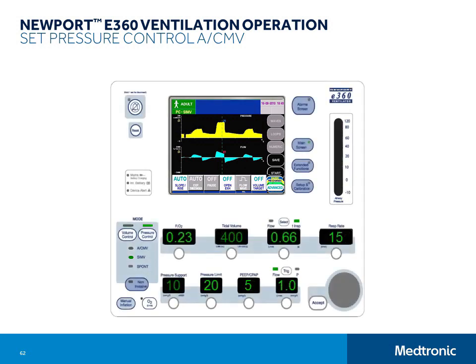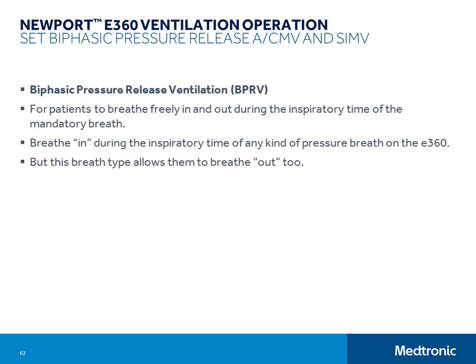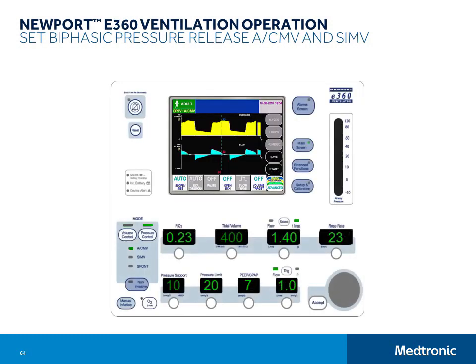We abbreviate this as BPRV. It is called bilevel or BiPAP or APRV on other products. Simply set the ventilator up for pressure control ACMV or SIMV, then turn on the open exhalation setting in the advanced data set. You will have to make sure volume target is off. You will see that all of the same settings that were available in pressure control are still available in BPRV, but you will think of some of these settings a little differently now.